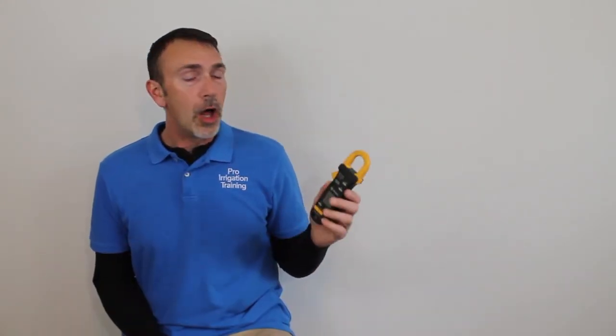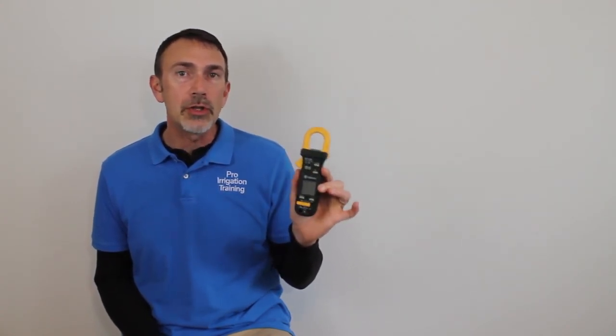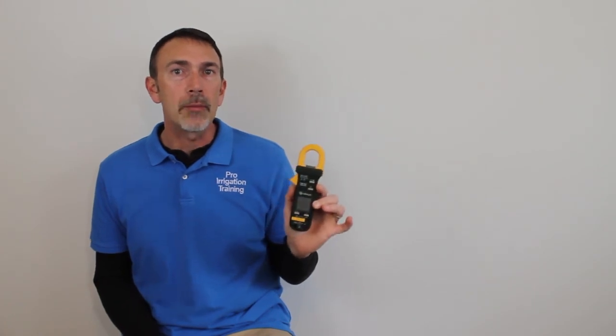Some of these good meters will also have a setting that'll allow you to measure the inrush amperage, so you can have this thing connected, turn the pump or appliance on or whatever you're trying to measure, and it will read the peak amperage, and consider that the inrush amperage, and also give you the operating amperage as well.